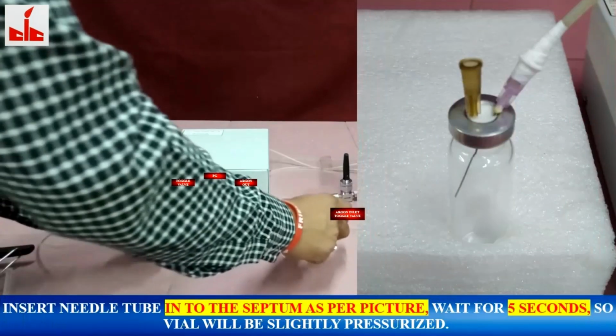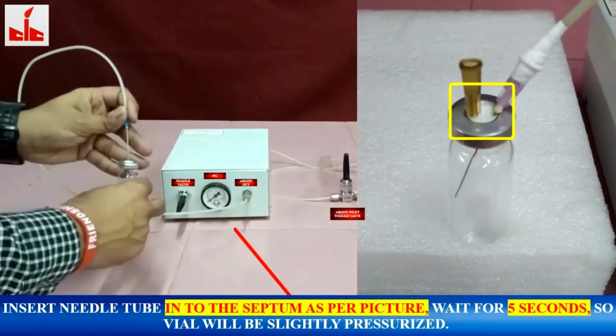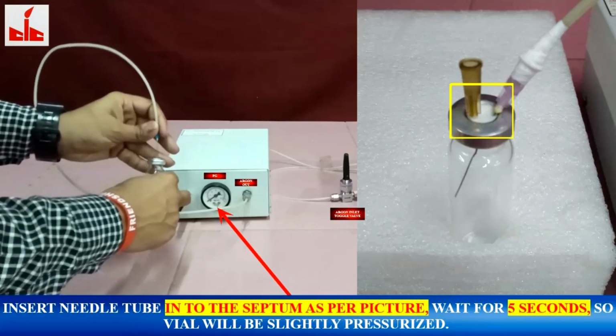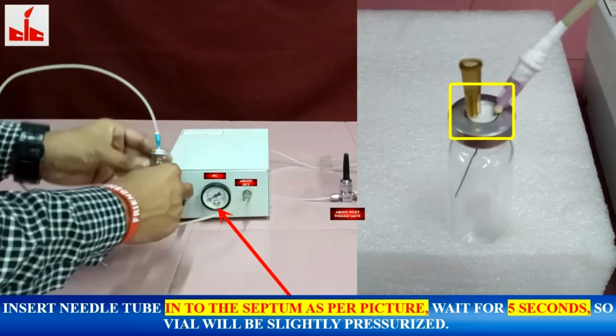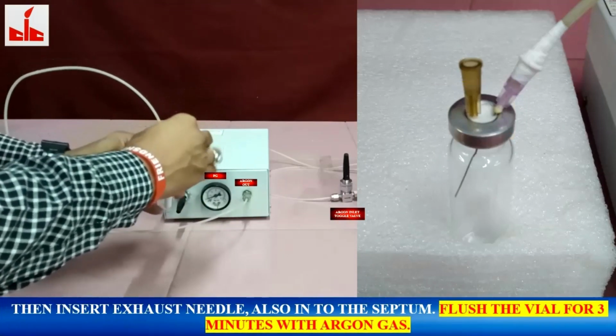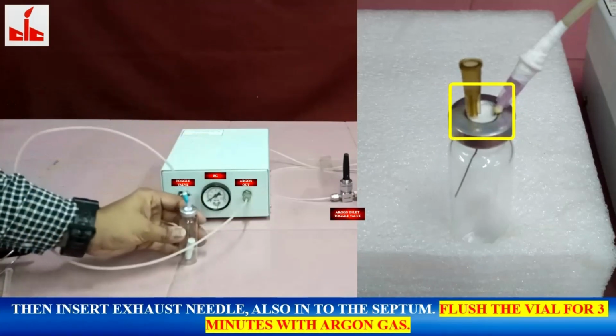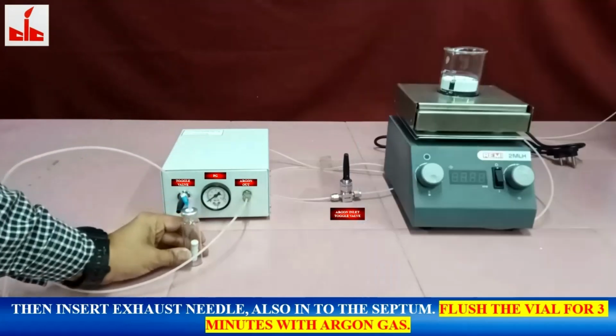Insert the needle tube into the septum as per the picture, and wait for 5 seconds so the vial will be slightly pressurized. Then insert the exhaust needle also into the septum. Flush the vial for 3 minutes with argon gas.